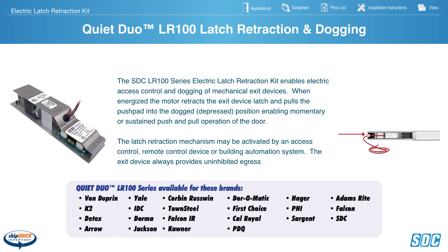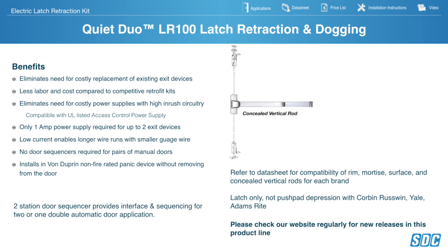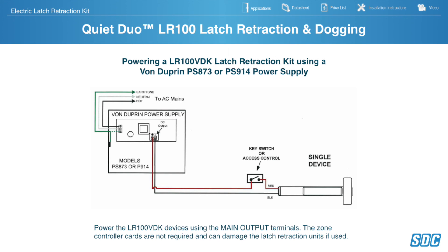SDC QuietDuo LR100 Latch Retraction and Dogging Kit is designed to retrofit panic devices in the field. It uses a worm drive motor for quiet operation and low power consumption — 700mA latch retraction and 180mA to dog it. When energized, the motor retracts the latch and pulls the push pad in, enabling momentary or sustained push-and-pull operation. Dogging is accomplished by a built-in magnet that holds until access control times out or sustained dogging is set. Available in almost every brand, including the Von Duprin 33, 35, 98, and 99 series with or without vertical rods — installable in under 15 minutes with installation videos available on the website.